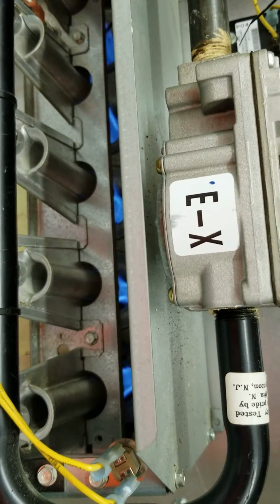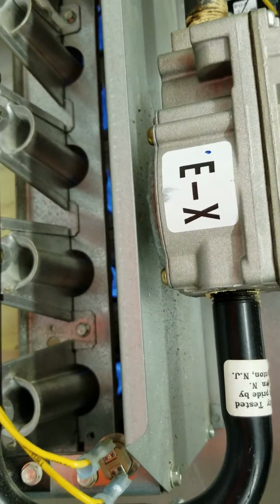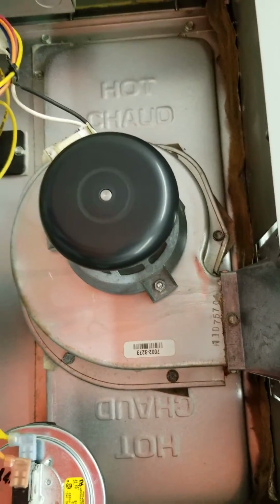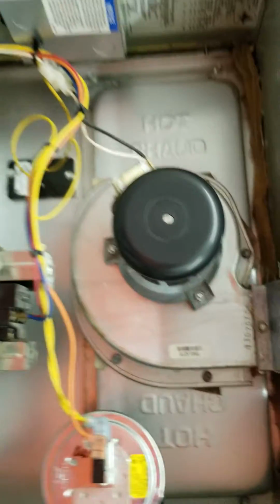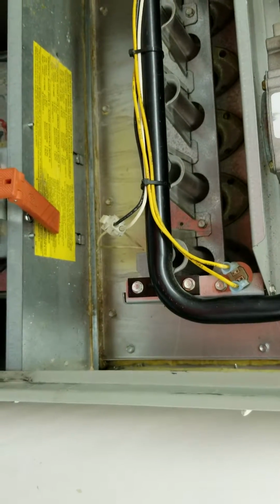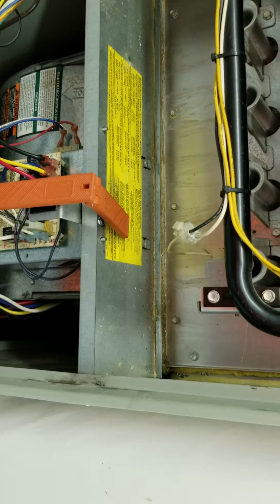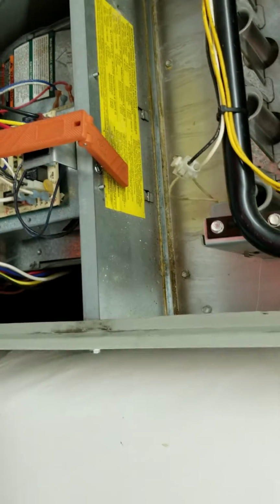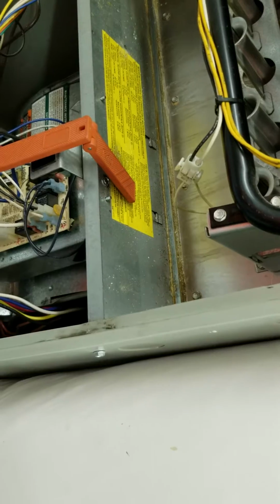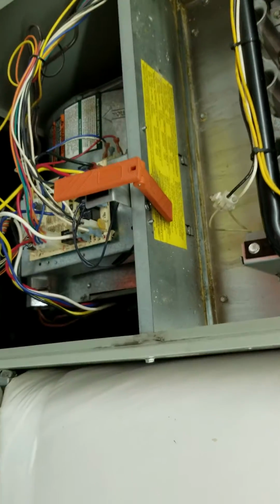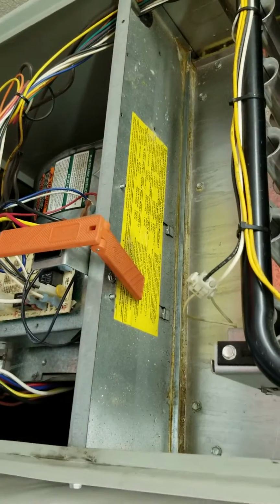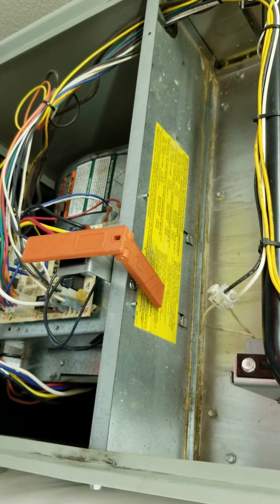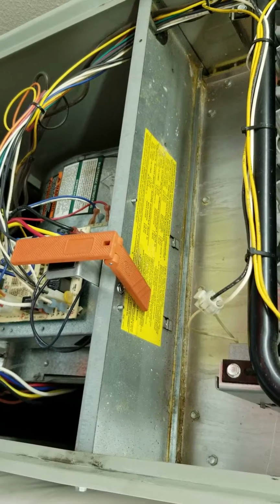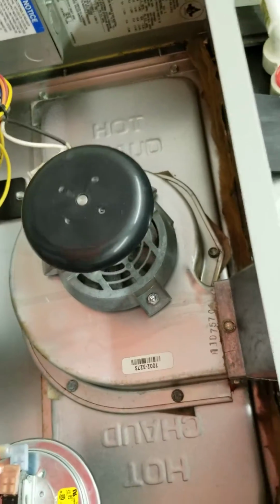Okay, it takes a few seconds. And there, our burner shut off. Our draft inducer shut off. You can see it slowing down. Now after a period of time, so many seconds, the blower will shut off. You want to let it run to the shutdown point. See, there's our inducer almost to a stop.